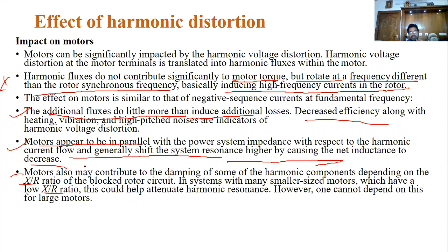Okay, now see this, some additional losses because of some additional flux. Additional harmonic current is injected into the system, that will also lead to some additional losses, which decreases the efficiency of these transformers. Whenever more motors are connected in parallel to this power system due to some automation necessity, the current flowing generally shifts the system resonance higher, which causes the inductance to decrease. So nothing but the X/R ratio. You know what that X/R ratio is? So this also changes.